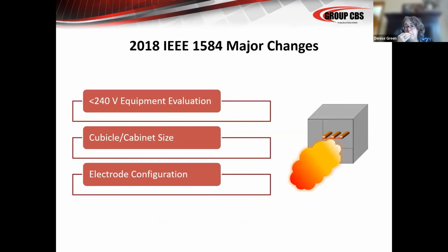So I see there's a question. This might be a good time to stop. Yes? Yeah, so the question is, what maintenance can you do to a molded case circuit breaker to take credit for the manufacturer trip times in an arc flash study?